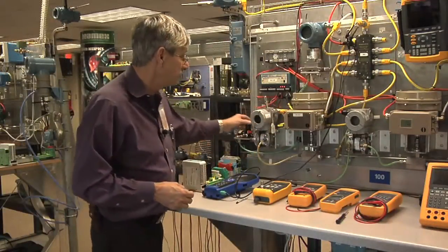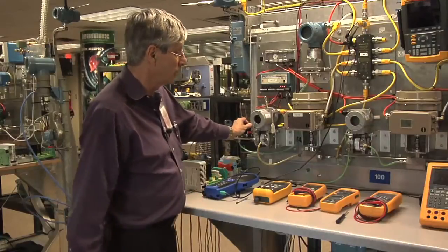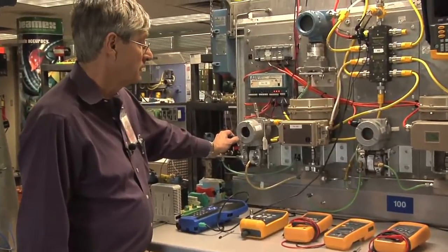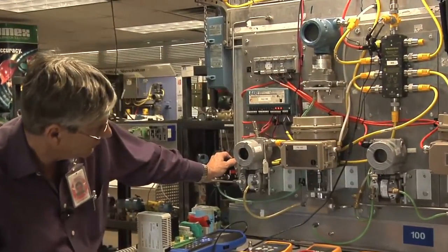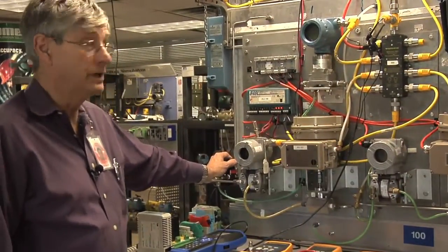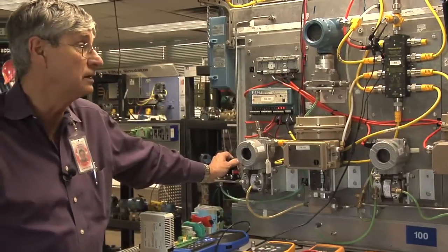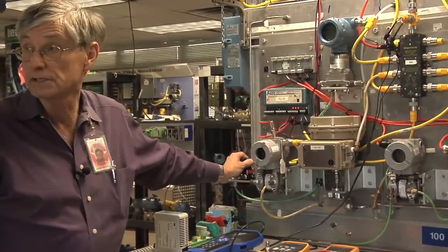And what I'll do is demonstrate that we are still attempting to control by basically reducing the pressure coming into my flow system. And again, we see the valve opening as I reduce my input pressure, trying to maintain the set point. So it's still operating.